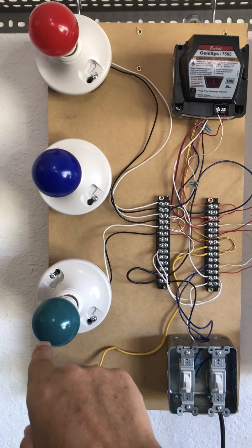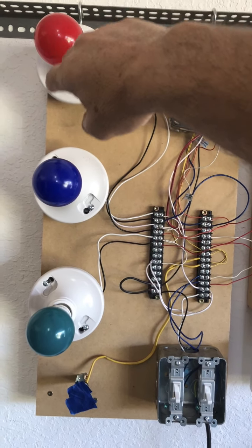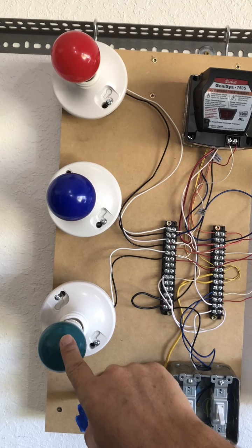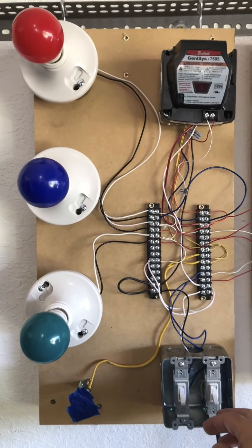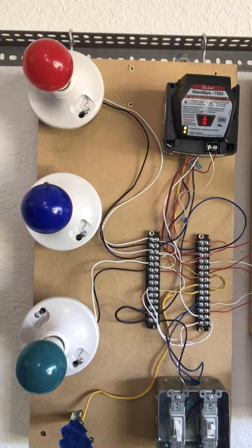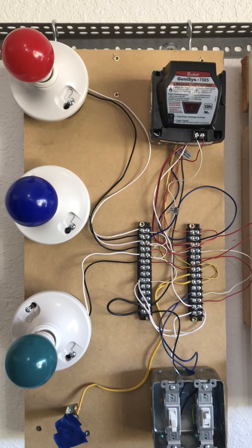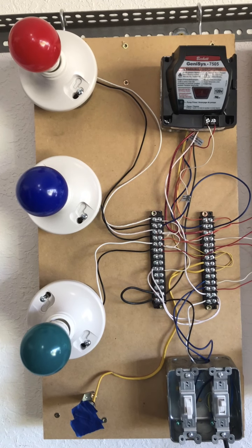I have my ignition up here, that's the red. I have my burner motor, that's the blue. And I have my oil valve solenoid, that's my green. So we turn power on, my ignition control, my primary control is right up here. When we turn the power on, our primary control will cycle through on and off for our power up, and it just sits here waiting on a call for heat.